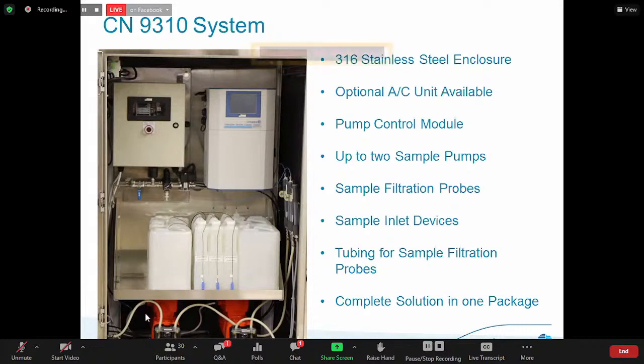On this side, the pumps would push the sample into these sample inlet devices. And when that stream is selected, then as we saw in the previous slide, the sample pump on board the instrument pulls the sample out of here and then through the flow path of the instrument. So what comes with the system, again, with the filtration probes, is the tubing for the sample filtration probes, and then this is a complete solution in one package. So we have the CN9310, the pump control module. This is for control of the sample probe, which I'm going to show you in a slide. And down below it would be our reagents and check standards that we need here, and would plumb to the instrument. So this is more or less a very basic system for the CN9310.